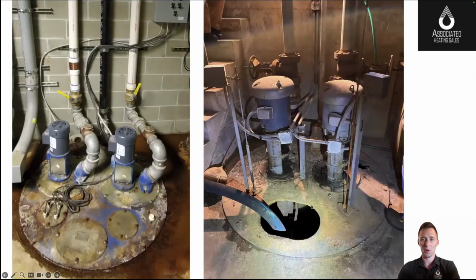So these vertical pumps, another nice part is if you see another brand that's obsolete, they don't make them anymore, Weil Pump is one of the pump companies that still makes these vertical pumps. It's very easy to retrofit onto these heavy duty covers where there's a standard opening size, typically 18 inches across.